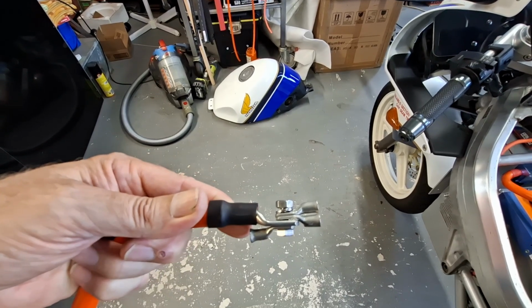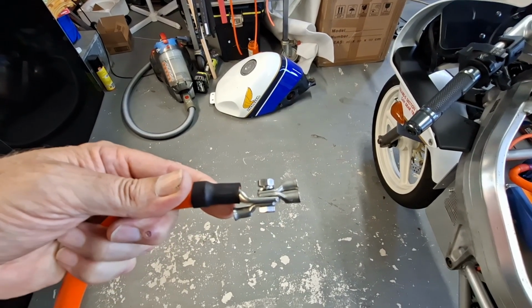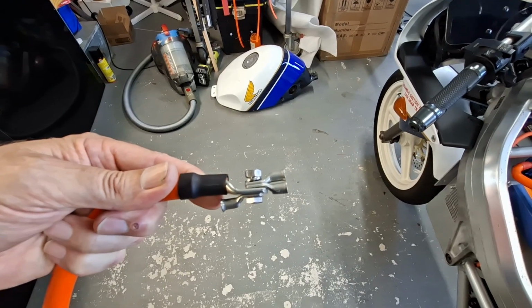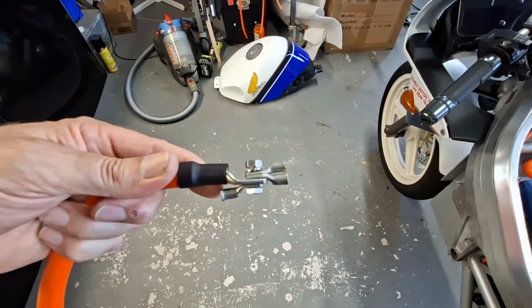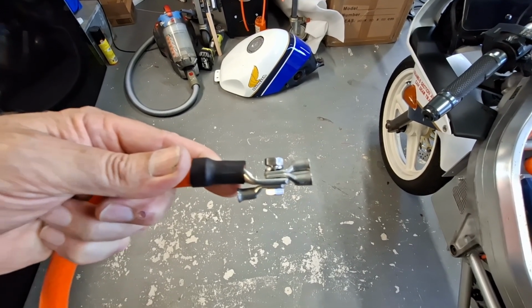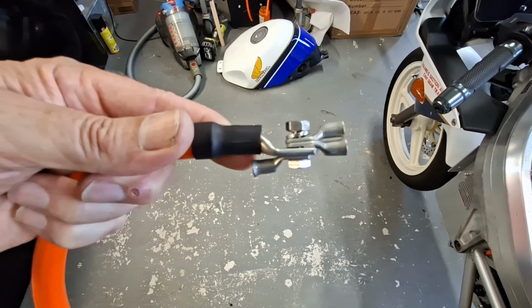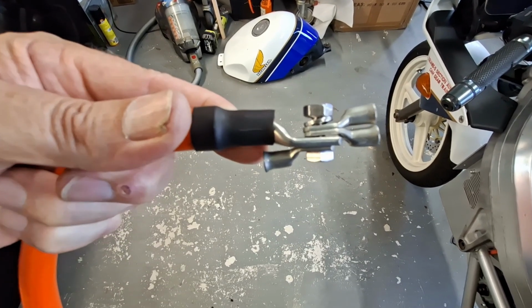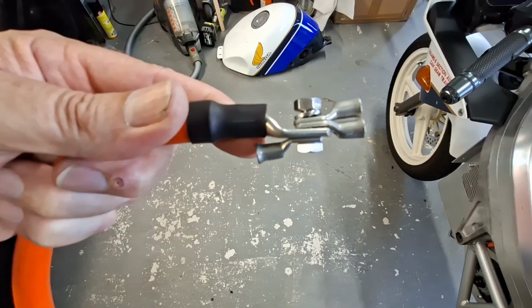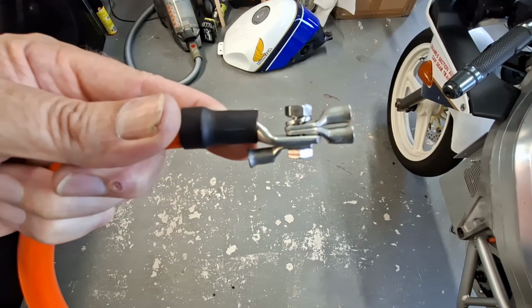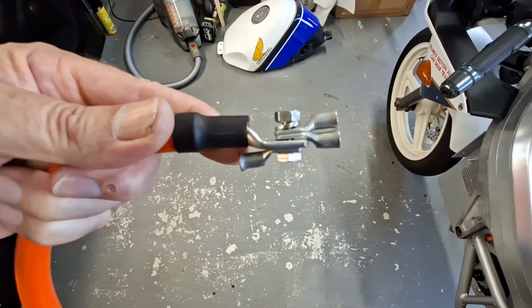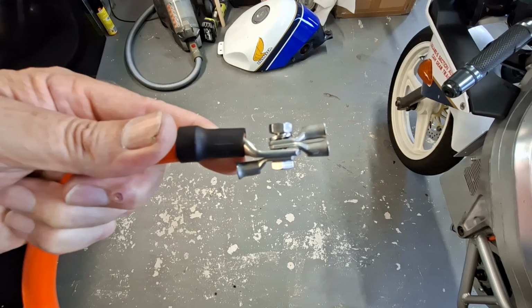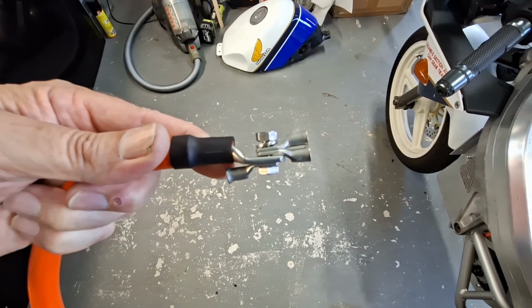I'll put two layers of heat shrink over it all to protect it from harm. It won't be an issue since there's no movement there to make them come loose. But there's a bit of a gap in how the lugs sit on top, so I need to file a tiny bit off the big lug so the two lugs on top sit flat, then I'll bolt it all in and tension it up.